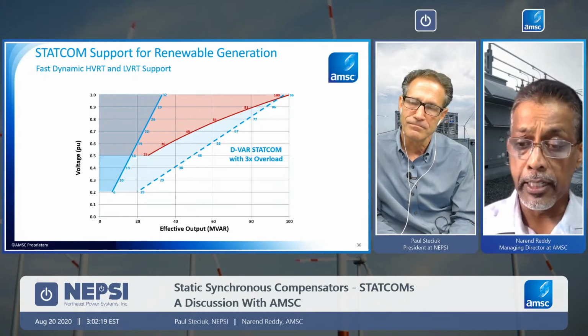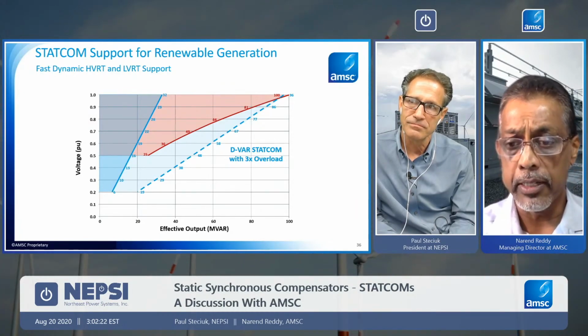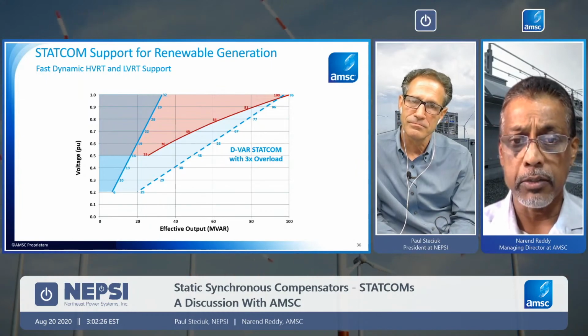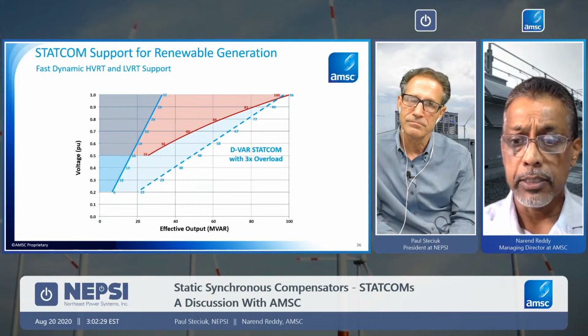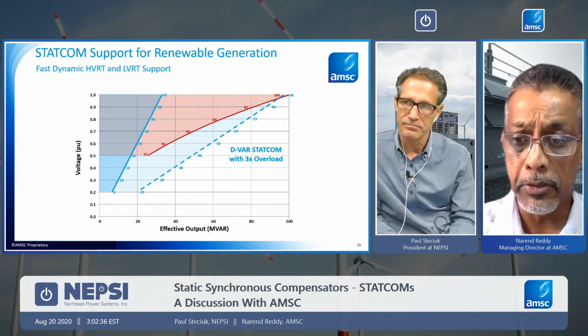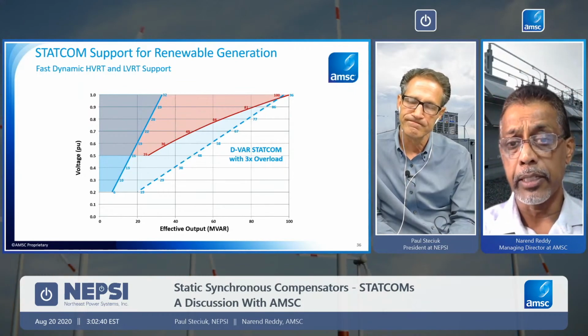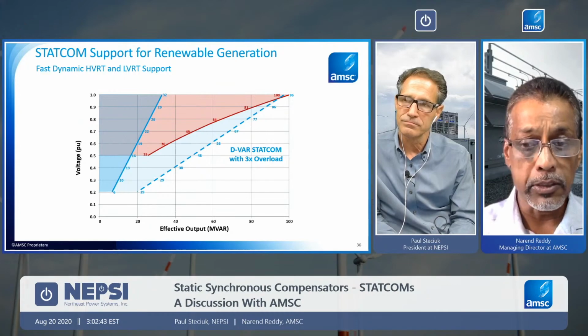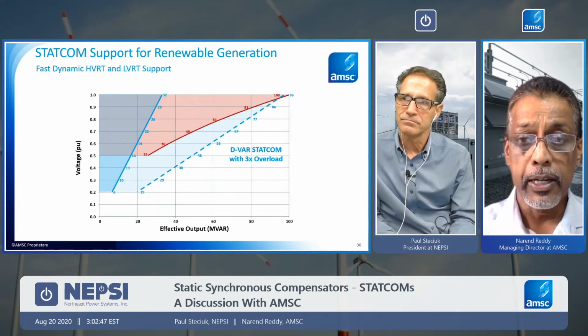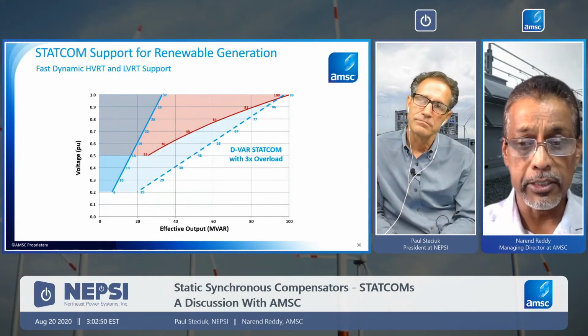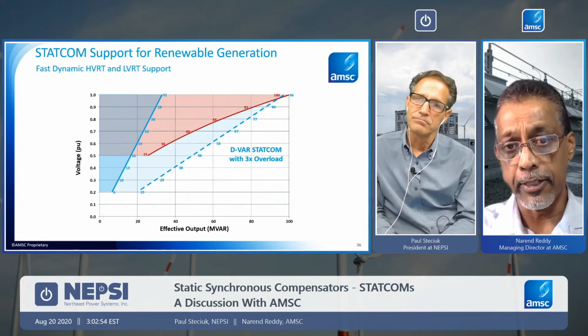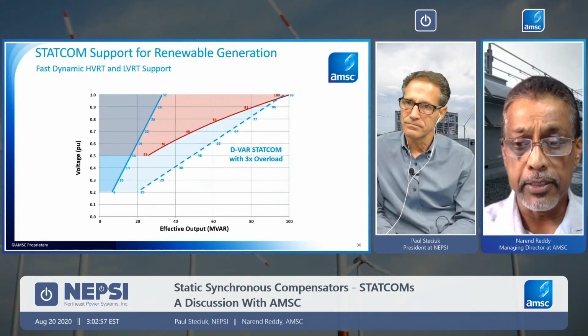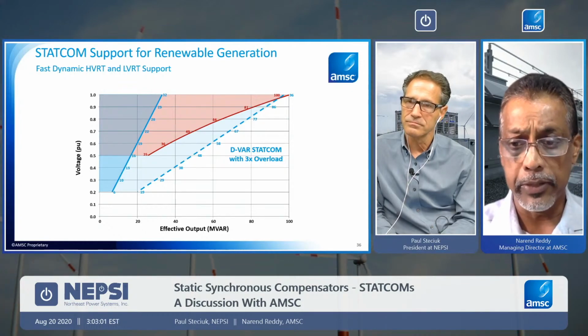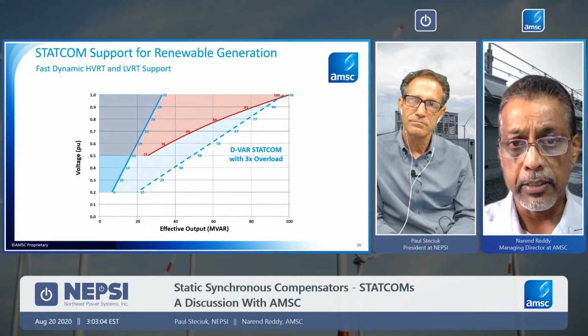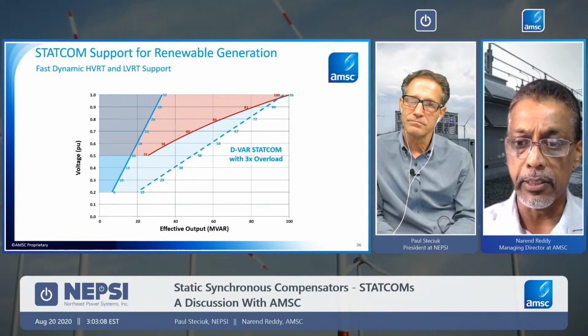And one of the key applications that we see, as I mentioned, is that we have about 123 systems that we have sold worldwide, supporting about 12 gigawatts of wind generation. A lot of these systems, the D-VAR units, because they are able to operate all the way down to 20% remaining voltage, really help provide low voltage ride-through, as well as in some cases high voltage ride-through support for some of these very strict grid interconnections. That's why I wanted to show the difference, and why STATCOMs are really part of the grid codes these days. If you look anywhere around the world, STATCOM is the product of choice for providing that additional voltage regulation.